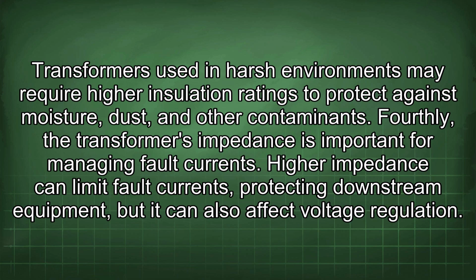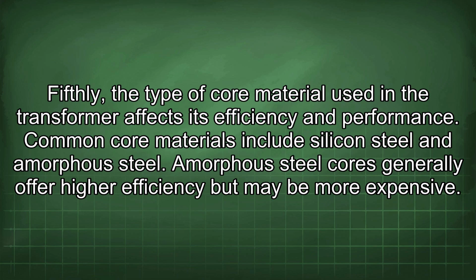Fourthly, the transformer's impedance is important for managing fault currents. Higher impedance can limit fault currents, protecting downstream equipment, but it can also affect voltage regulation. Fifthly, the type of core material used in the transformer affects its efficiency and performance. Common core materials include silicon steel and amorphous steel. Amorphous steel cores generally offer higher efficiency but may be more expensive.